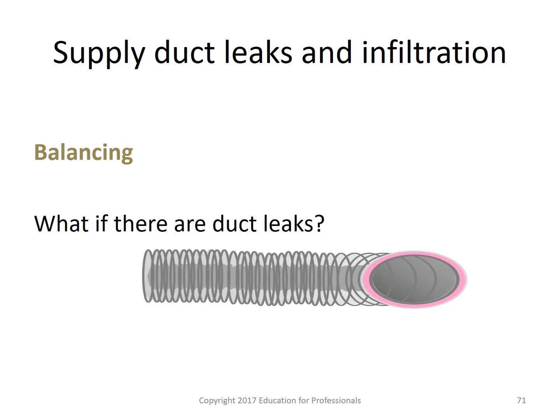And if supply ducts in unconditioned areas have more leaks than return ducts, heated and cooled air will escape to the outside, increasing energy costs, for one. Less air volume will be supplied to the building, so the pressure inside the building may become negative. This is what causes air infiltration, and the negative pressure can actually backdraft flues at the very extreme end, which would pull exhaust gases back into the home from fireplaces and combustion appliances. These health effects can be deadly if flues contain substantial carbon monoxide.